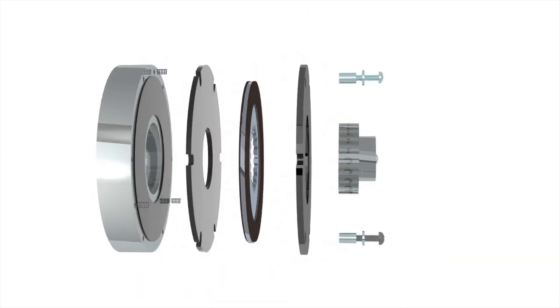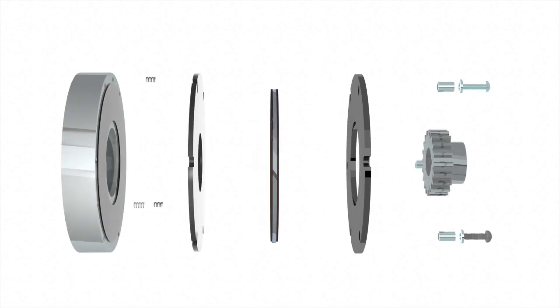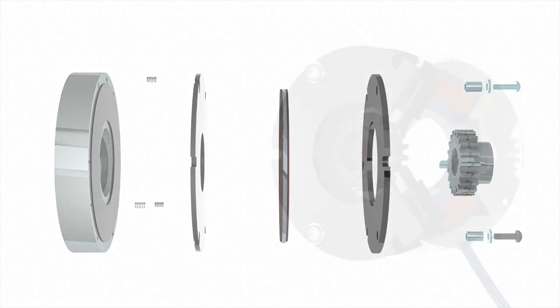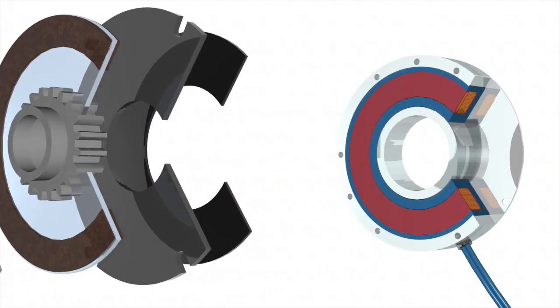The key components to the brake are the coil, springs, pressure plate, friction disc, cover plate, and hub. Spring-applied brakes transmit torque via spring pressure and use an electromagnetic field to release the spring pressure.